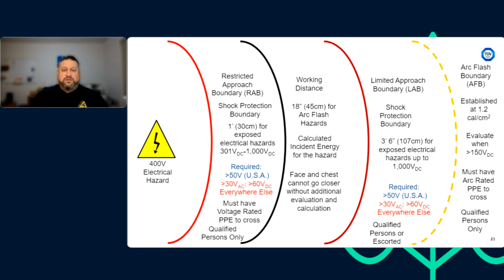So if we have a high voltage hazard, and that high voltage hazard has an arc flash hazard along with it, meaning that we have a heat energy that's exceeding 1.2 calories per centimeter squared, that means we have to establish an arc flash boundary. 1.2 calories per centimeter squared is the amount of heat energy that would start to give us second-degree burns. So if we're going to cross this arc flash boundary, all exposed skin, and all exposed non-rated apparel like a shirt, would all have to be covered by arc-rated PPE.